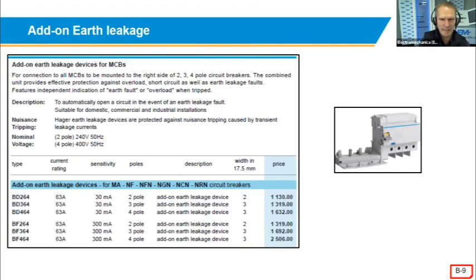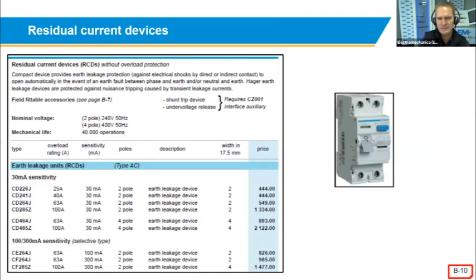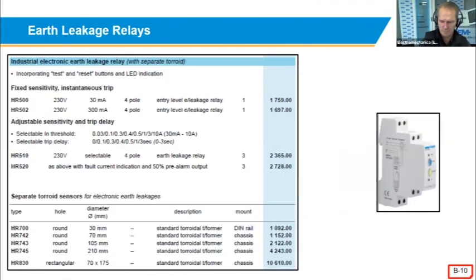Then the different add-on blocks, earth leakage devices that you can get for the different miniature circuit breakers, different milliamp settings, 30, 300 milliamps, 2-pole, 4-pole devices, 3-pole devices, all depending on where you want to use it. The normal residual current devices, the units without the overcurrent short circuit protection, which is an isolator type earth leakage device. The earth leakage relays that I mentioned, the different units from Hager that are available. Keep in mind that there are also the others from Lovato and Socomec.